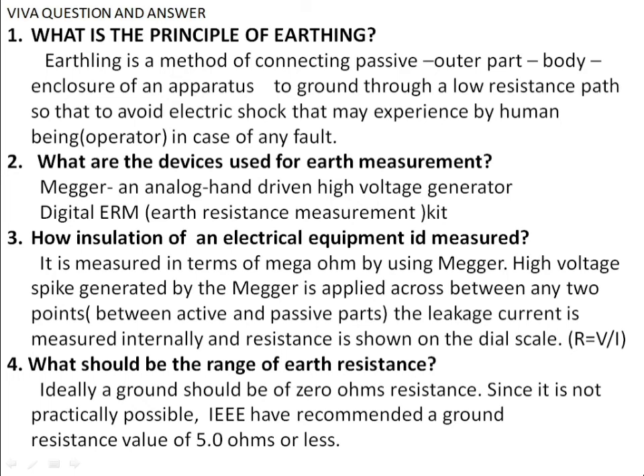How is insulation of an electrical equipment measured? It is measured in terms of mega ohms by using a Megger. It is used to measure the insulation also. The high voltage spike generated by the Megger is applied between any 2 points of the insulation, between the active part and the passive part. The leakage current is measured internally and the resistance is shown on the dial scale, R equals V by I.